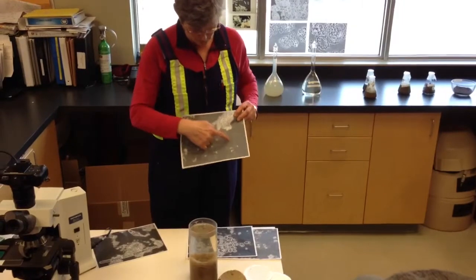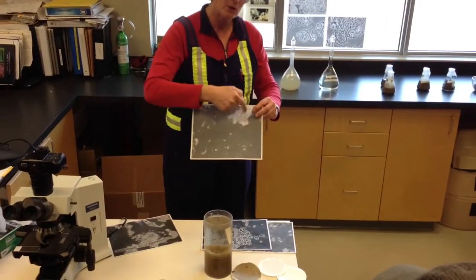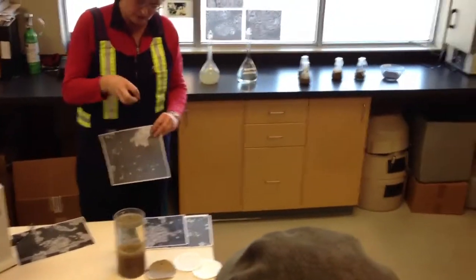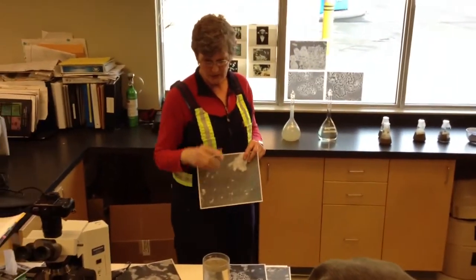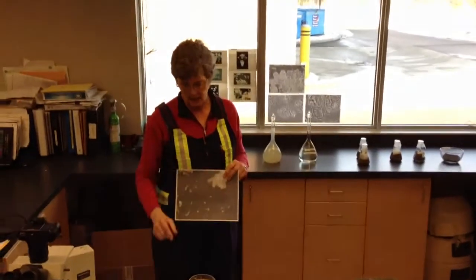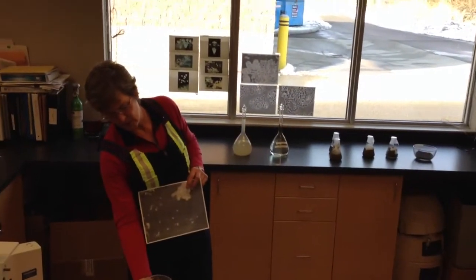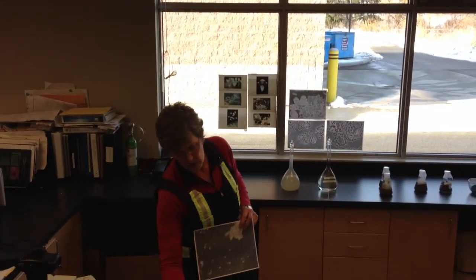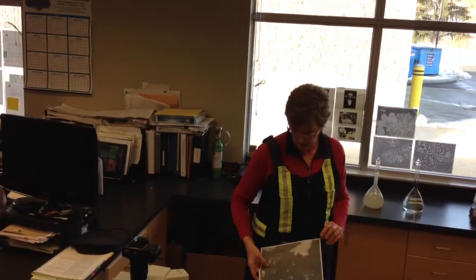We need some of the filamentous bacteria just because they form a framework, a skeletal kind of structure that the flocculating bacteria can clump to, but filamentous bacteria don't settle as well as the flocculating. So we want to have mostly the flocculating bacteria so that the solids will settle, and then we can remove the solids from the liquid portion.